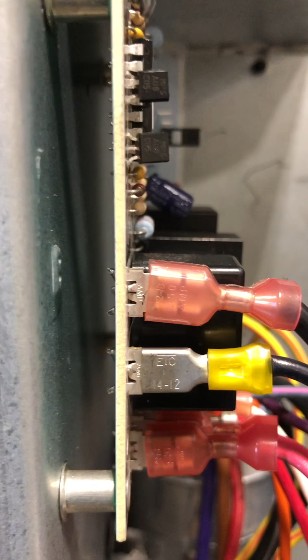So what I've run into a lot of the time is right behind this board. See, there's a nice space through there, but a lot of times what happens is spiders and stuff will crawl up in there and build their nests because it's nice and warm. And all those little solder joints there, we get enough spider webbing back in there, and it makes an electrical connection from the board to the case of this heat pump and shorts this board out. And we got to change that board. But that controls our defrost cycle.